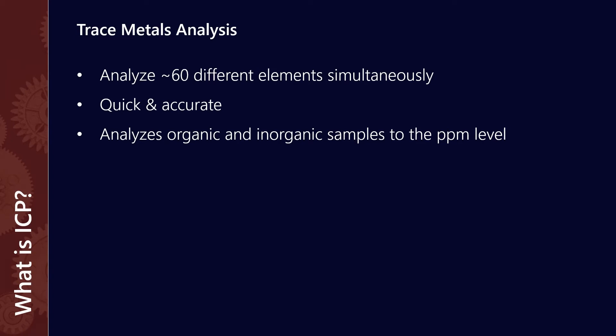What it's used for and what it's really good for is analyzing a whole bunch of different elements samples simultaneously. So with one sample you can get a lot of different results at the same time using the same equipment. It's also very fast, quite accurate, and it also analyzes both organic and inorganic samples to the parts per million level. It's not just oil analysis that takes advantage of these testing methods. You can test a variety of different materials. The key is that it needs to be soluble because the sample needs to be aerosolized in order to get a good reading.